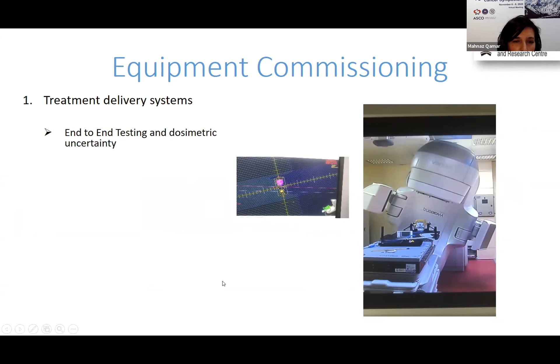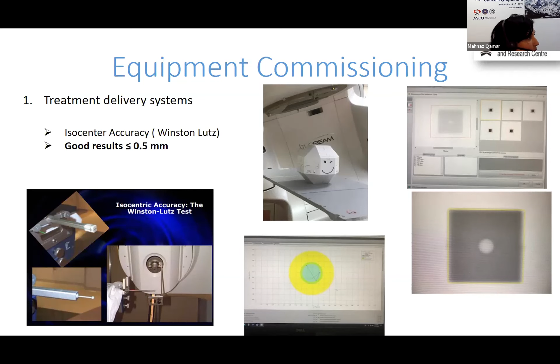Then you have to check the isocenter accuracy of your machine with the famous Winston Lutz test. There are different ways of doing it. Different phantoms are available in the market where you can image and then send the images to a system that analyzes the isocenter accuracy and comes up with a number. This is required to be done before every patient treatment.